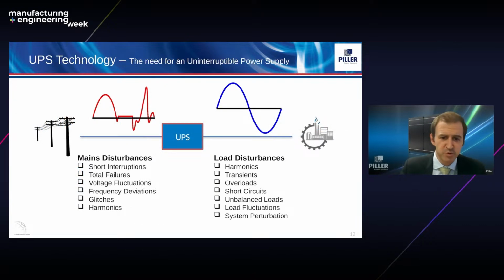So an uninterruptible power supply, or UPS, it's not there just to protect in the event of a complete loss of power, which is what most people think of them to be. They are actually there offering constant power conditioning to your critical loads, providing a constant clean supply of power irrespective of the quality of the supply from the grid, from generation sources, or even from no grid at all.